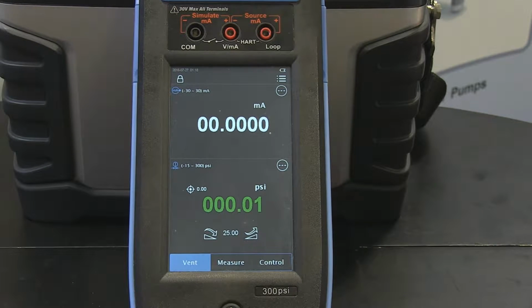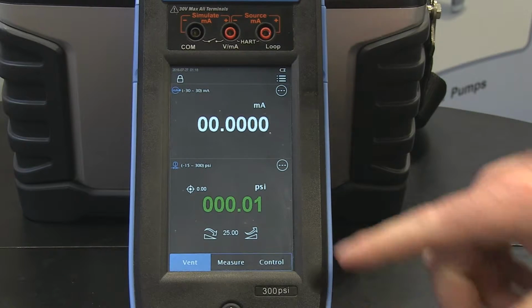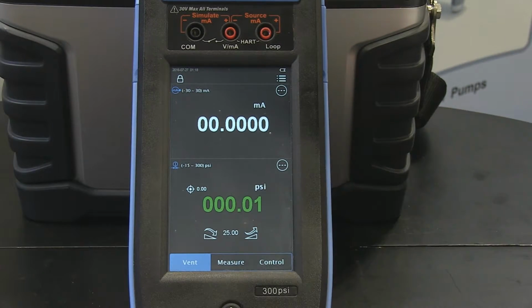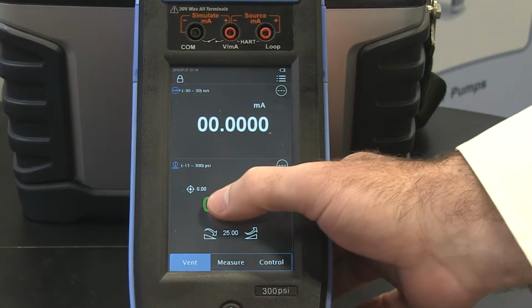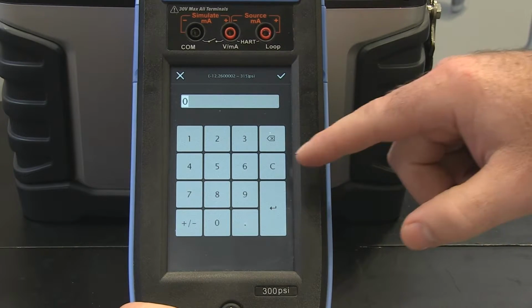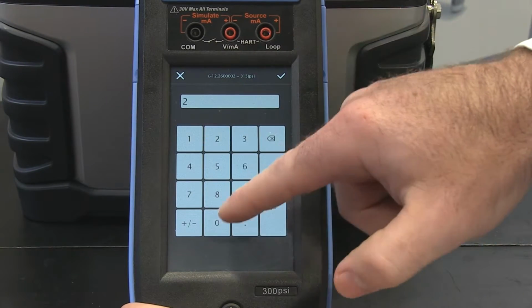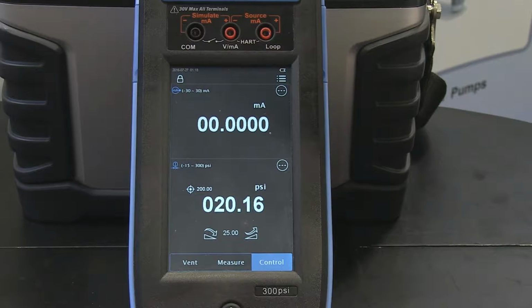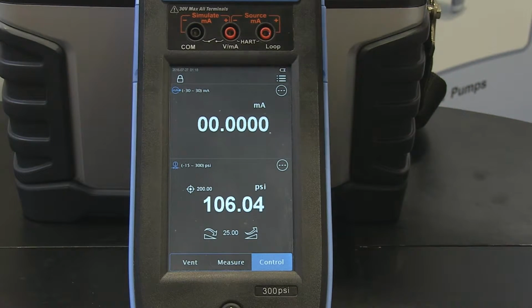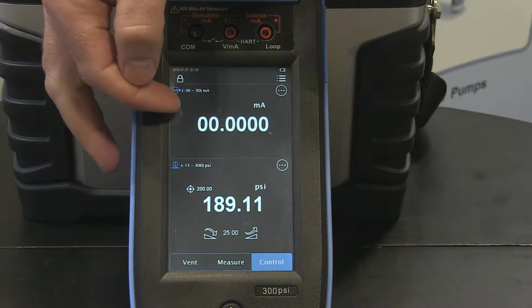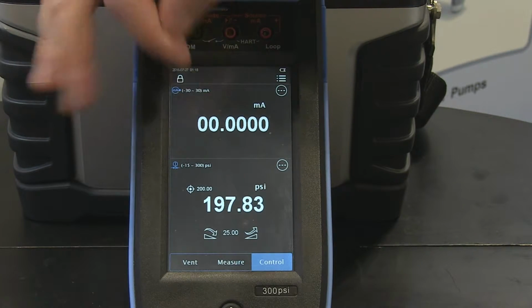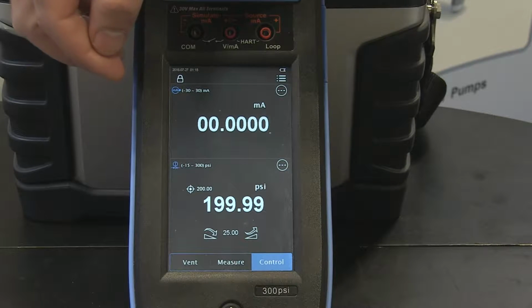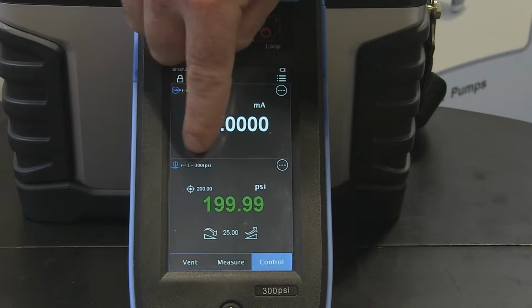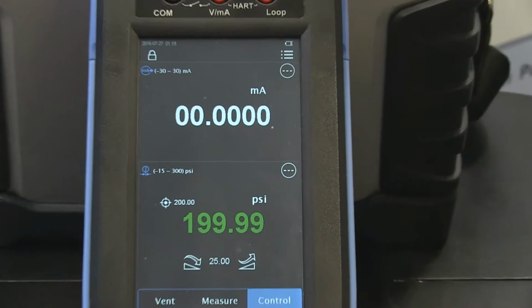Okay. So each unit comes with one sensor, as mentioned before. That main primary sensor is being shown here. The most basic thing done with this unit is you set the pressure and generate pressure. So everything is touchscreen on this. Say we want to go to 200 PSI, then it'll generate pressure. You can see on the screen, just to orient you a little bit, as this is generating pressure, you've got your current measurement here, or it could be voltage. This would be what you're measuring with the process calibration portion of it. This is the pressure range of the sensor displayed there. I'll zoom in a little just so we can see.